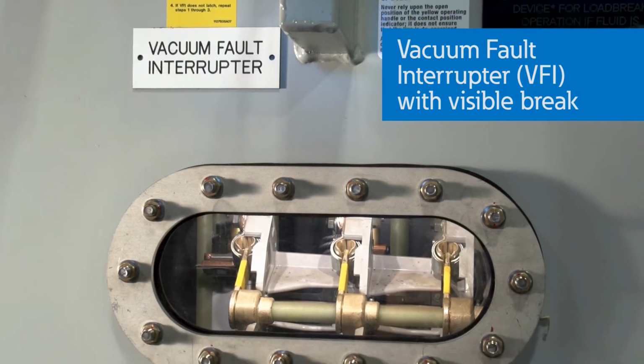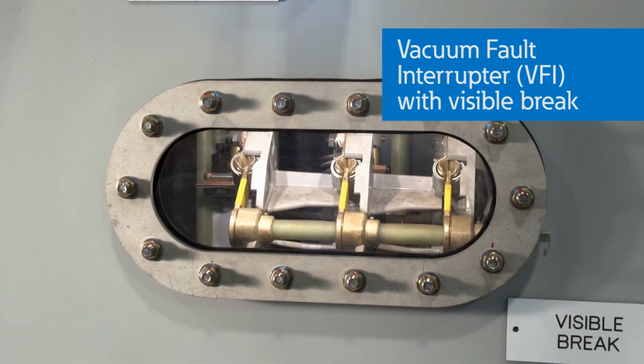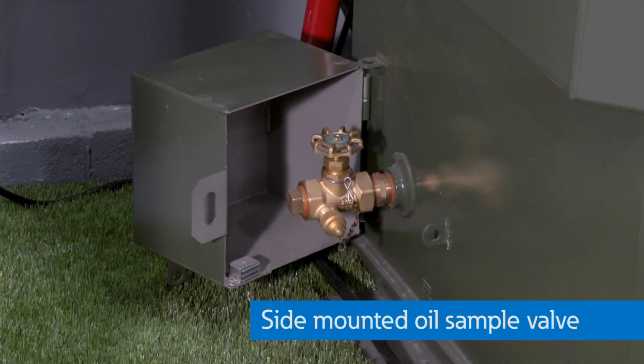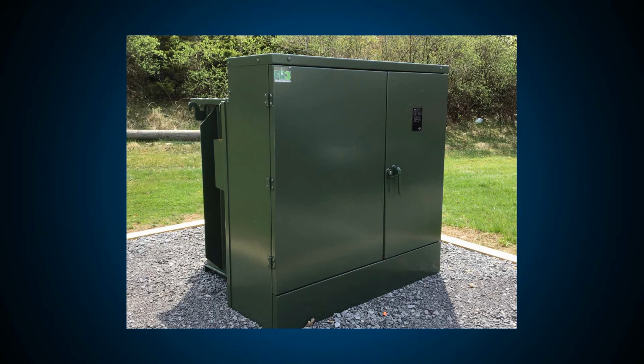Basically, with the same type of concept, we can install that primary breaker inside a liquid-filled transformer. For liquid-filled transformers, you might want to consider a vacuum fault interrupter, or VFI option like this one, which allows you to have the primary protective device, a vacuum breaker, installed in the tank along with the visible means of disconnect. In addition, you could also put the oil sample valve on the side like this transformer instead of behind the door. This allows you to do oil testing without opening the transformer doors on a pad-mounted transformer like this one.